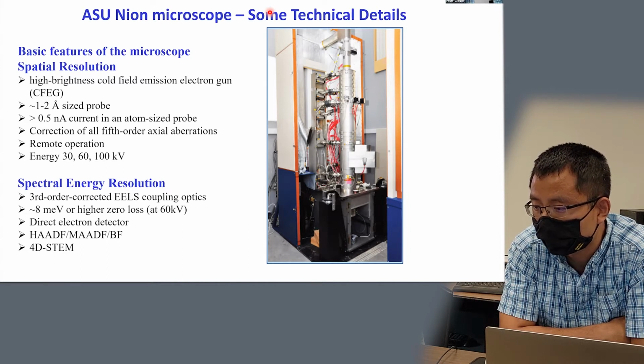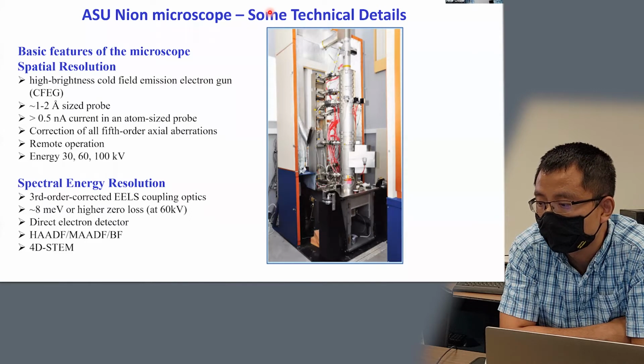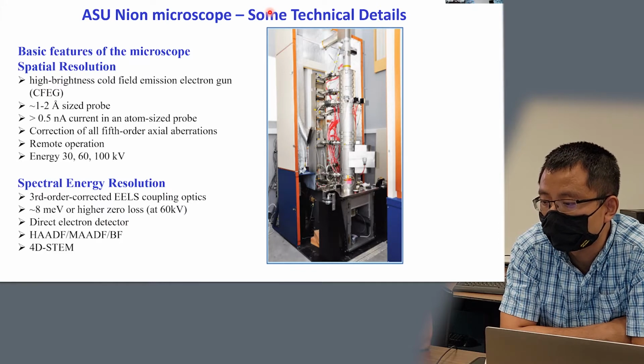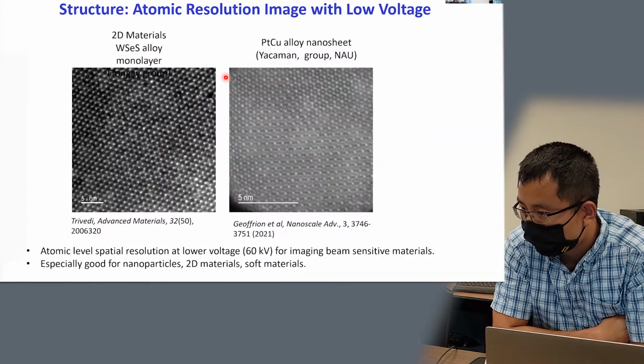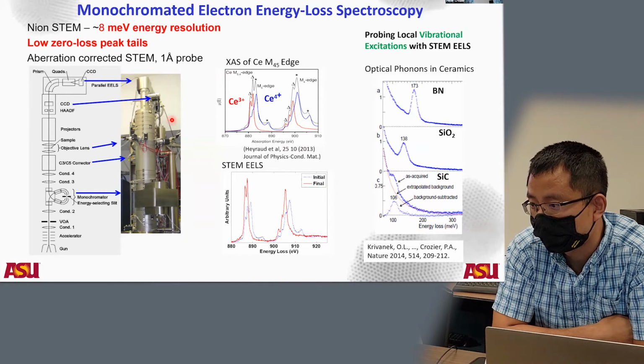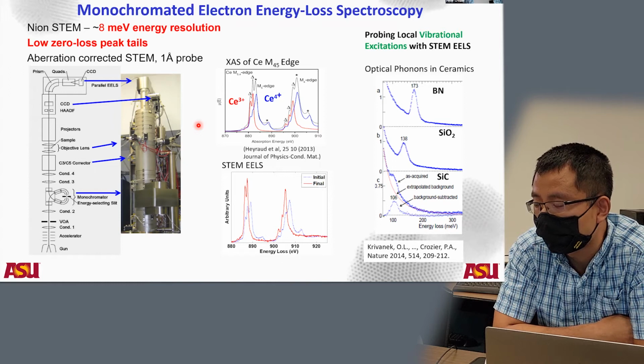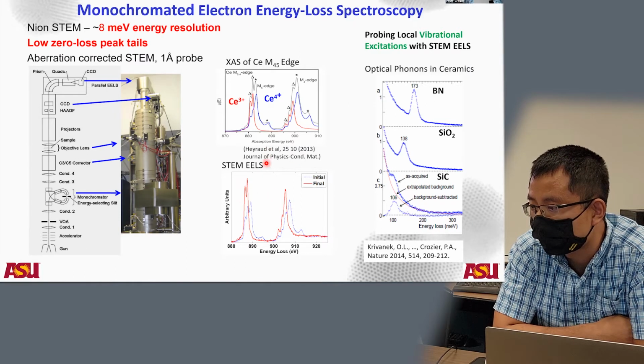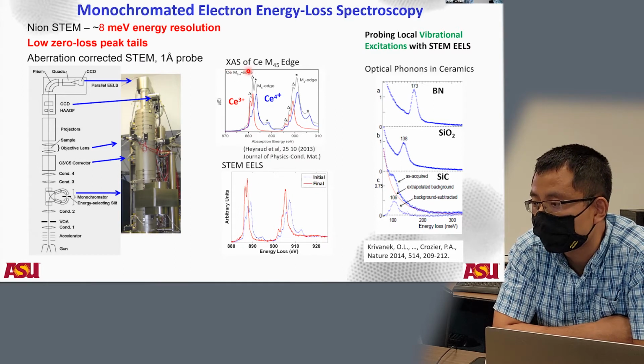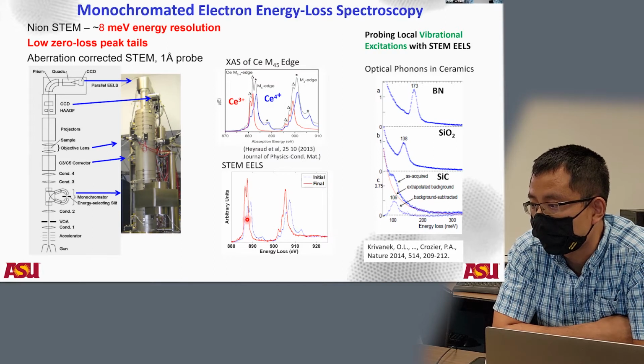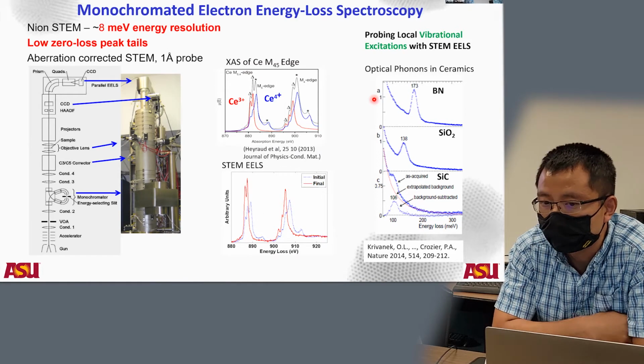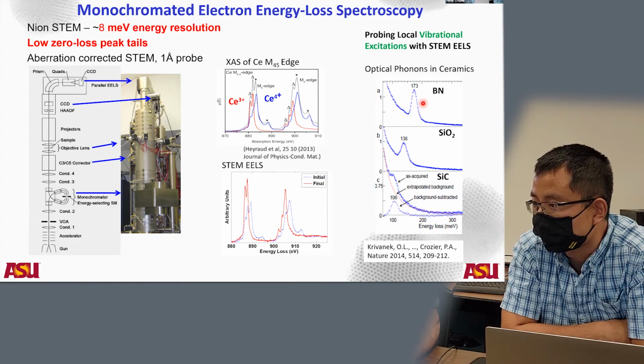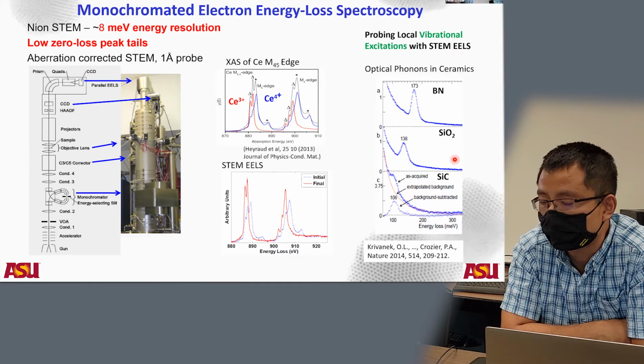In terms of EELS capability, we can achieve as high as 8 millielectron volt at the zero loss peak at 60 kV. With the new direct electron detector, we can do a lot of fancy techniques, such as 4D STEM, along with the normal high-angle, medium-angle annular dark field, and bright field imaging modes. With the core loss, for example of cerium, we can achieve decent energy resolution, comparable to X-ray absorption, to resolve the valence state of cerium atoms. And with the low loss capability, we can measure phonon signals in different materials such as boron nitride, silicon oxide, and silicon carbide.